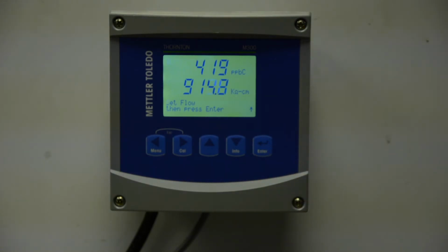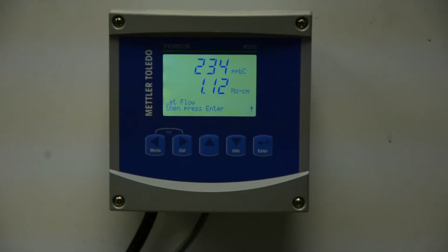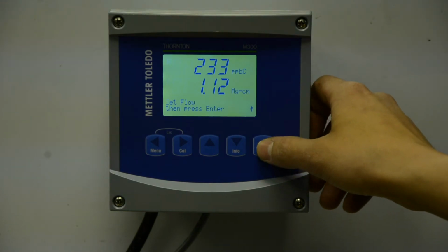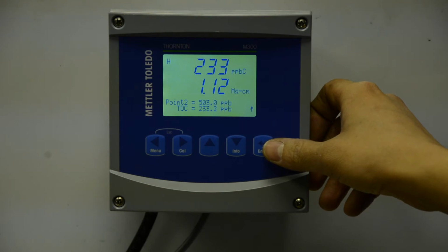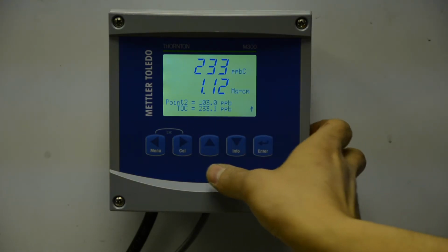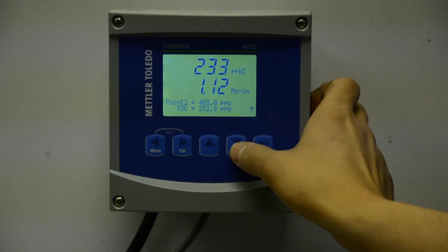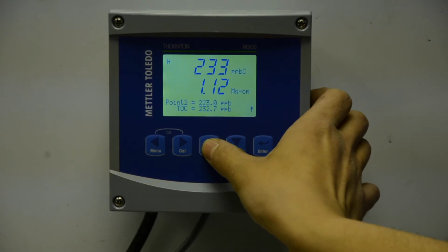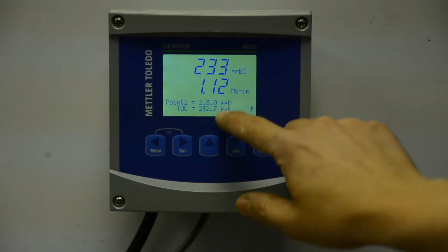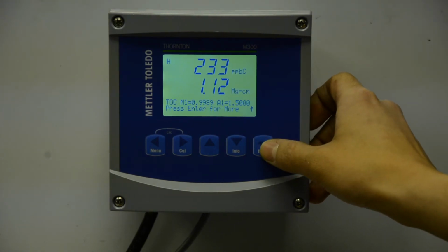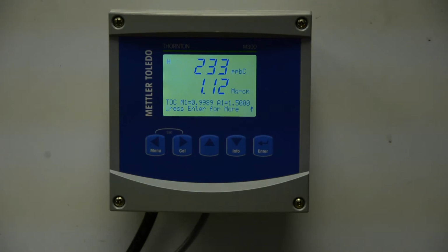Next, it will ask you to set a new flow rate. You have to stop the 500 solution. Now you want to put the 253 parts per billion solution in and let that stabilize. Once your reading is stabilized, readjust your flow, making sure that you have all 4 lights on, then press Enter. It will now ask you what your point 2 is. Enter in 253 parts per billion. And right now it's reading 233, and hit Enter. This will perform the second part of the calibration.